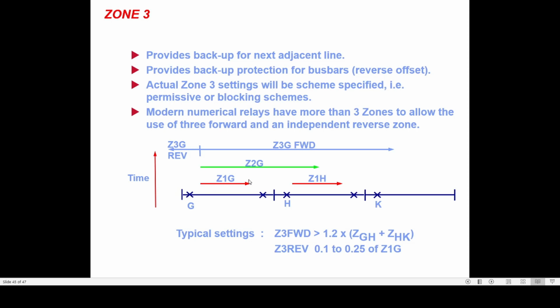up to this point, what we have considered is for zone 1, zone 2, zone 3, everything is that. The error is from this point. But while considering from right to left, there might be the chance that there are some cases in which the fault is, suppose, in the bus bar at substation G, but the relay at substation G, due to the error in measurement, sees this fault in the forward direction and this relay might operate. Now, to avoid all these conditions, some reverse looking zones are provided.